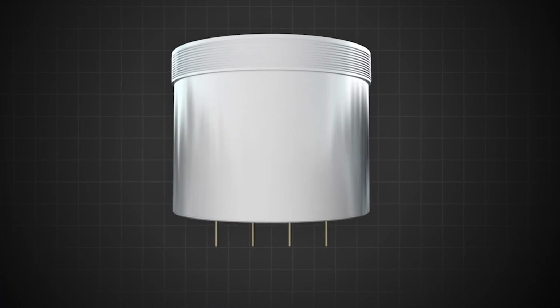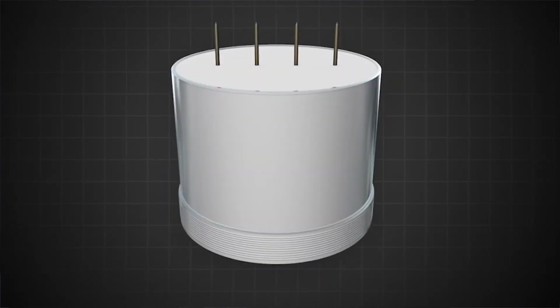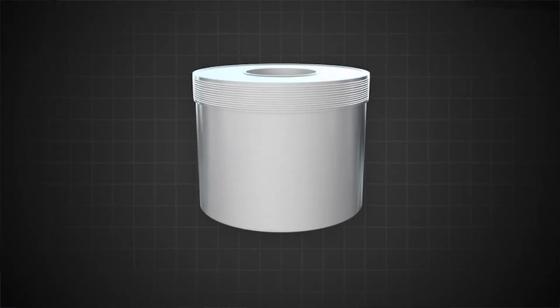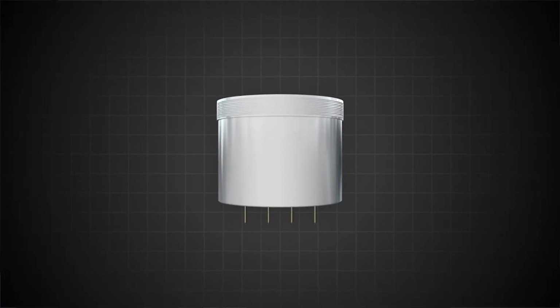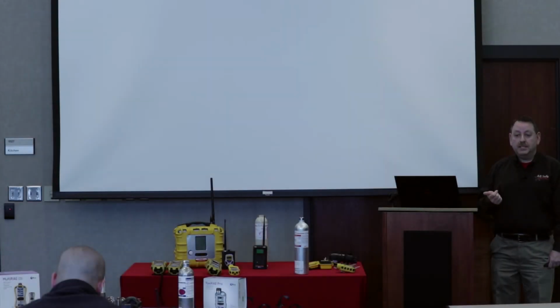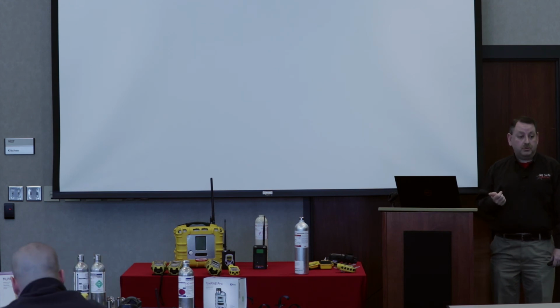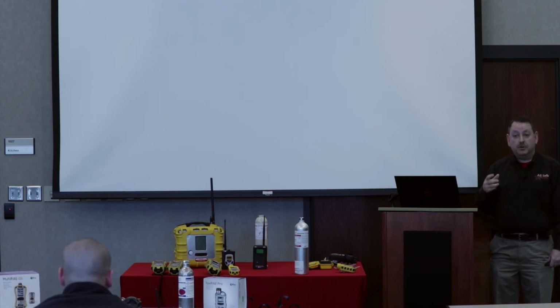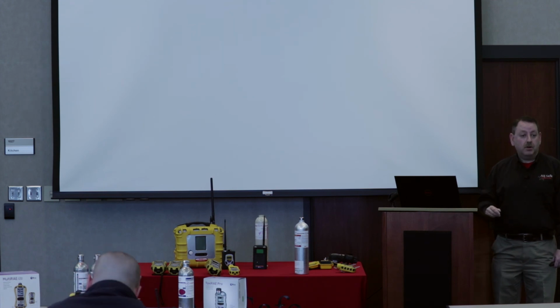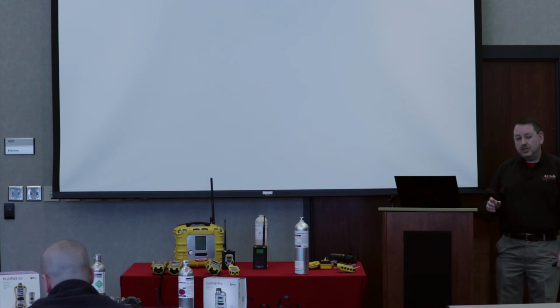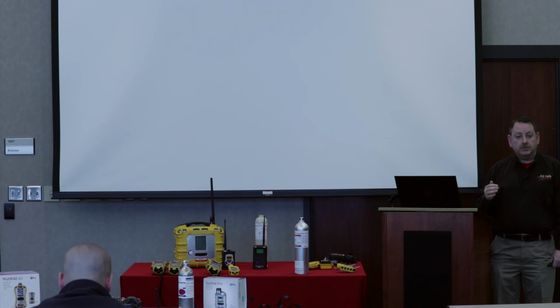So a little side note is that your LEL sensor, when it gets all the way to 100, it believes it's in a flammable atmosphere, and it will actually turn the sensor off, because we don't want the LEL sensor to be the source of ignition, of course, and we certainly wouldn't want it to burn out. You could burn up an LEL sensor all in one sitting if it just sits at 100, and so it will actually turn the sensor off. So the only way to reset that is to leave the space, turn the meter off, turn it back on, let it go through its new warm-up sequence. Okay? So any questions about the sensors that we just talked about, the oxygen sensor, the toxic sensors, or the LEL sensor?